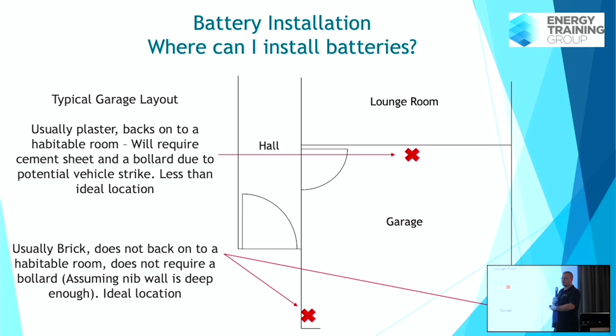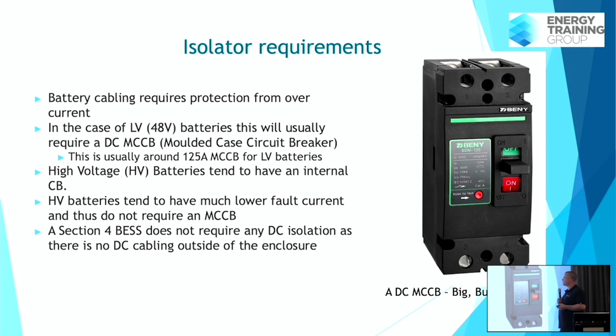Isolators. Okay, now, if you are doing 48 volt batteries, so low voltage batteries, you will find you need to install a molded case circuit breaker, unless the circuit breaker is built into the inverter, into the battery, and readily accessible. However, most of your 48 volt batteries do not have a readily accessible molded case circuit breaker in them. So you're going to have to install something that looks like this. These are around 150 bucks, right? They're not a cheap item. So sometimes this can really tip a 48 volt battery over the limit of being more expensive than a high voltage battery because you need more gear to install it, right? Low voltage batteries run at much higher current. That's why they require molded case circuit breakers and not your standard miniature circuit breaker, okay?